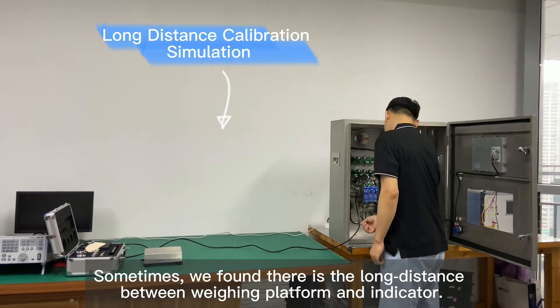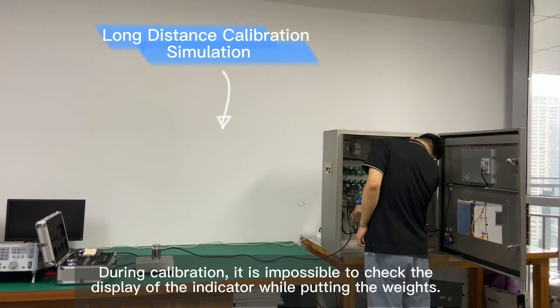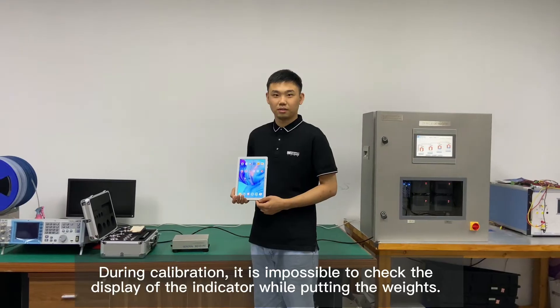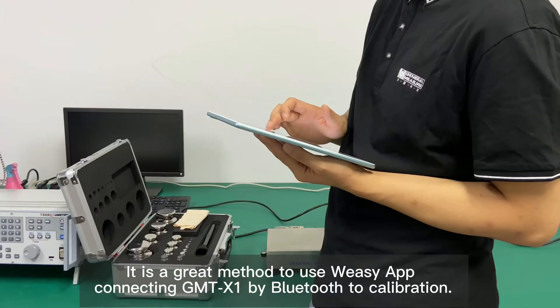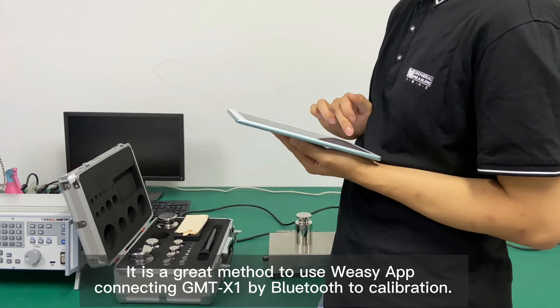Sometimes we find there is a long distance between the weighing platform and the indicator. During calibration, it is impossible to check the display of the indicator while putting the weights. Under such circumstances, it is a great method to use Weasy App, connecting to GMT-X1 by Bluetooth, to perform calibration.